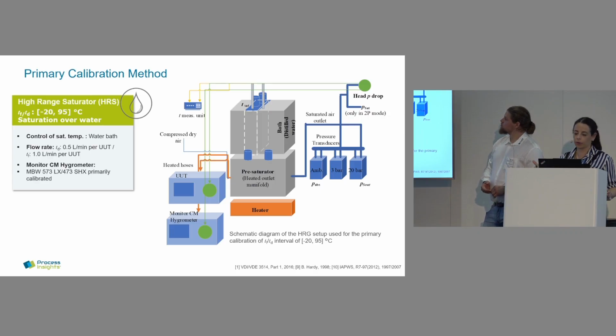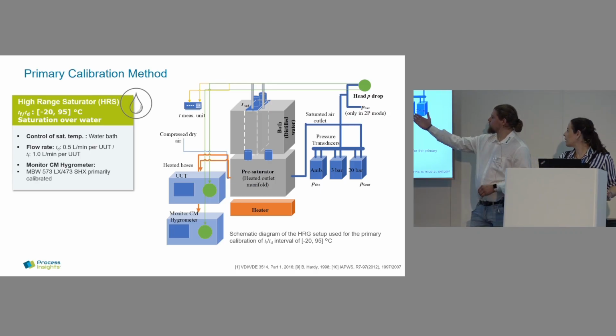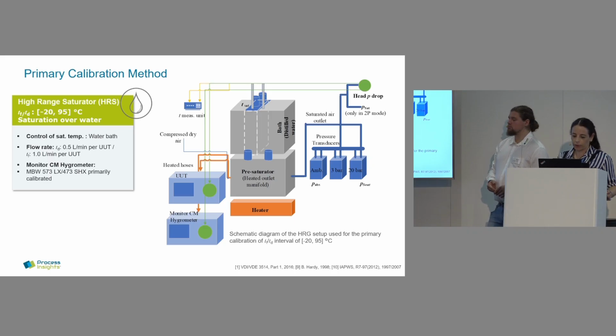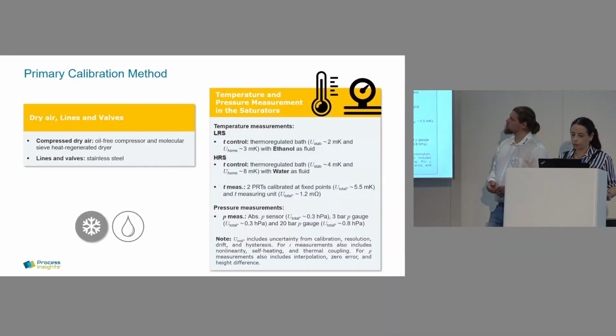Again, we need to measure the pressure. So 20 bar or 3 bar, depending on whether you are going to 2 pressure, we need these 2 pressure sensors, and then ambient pressure. Of course, all the compressed air needs to be clean from oil and very dry. All the lines are made of stainless steel.